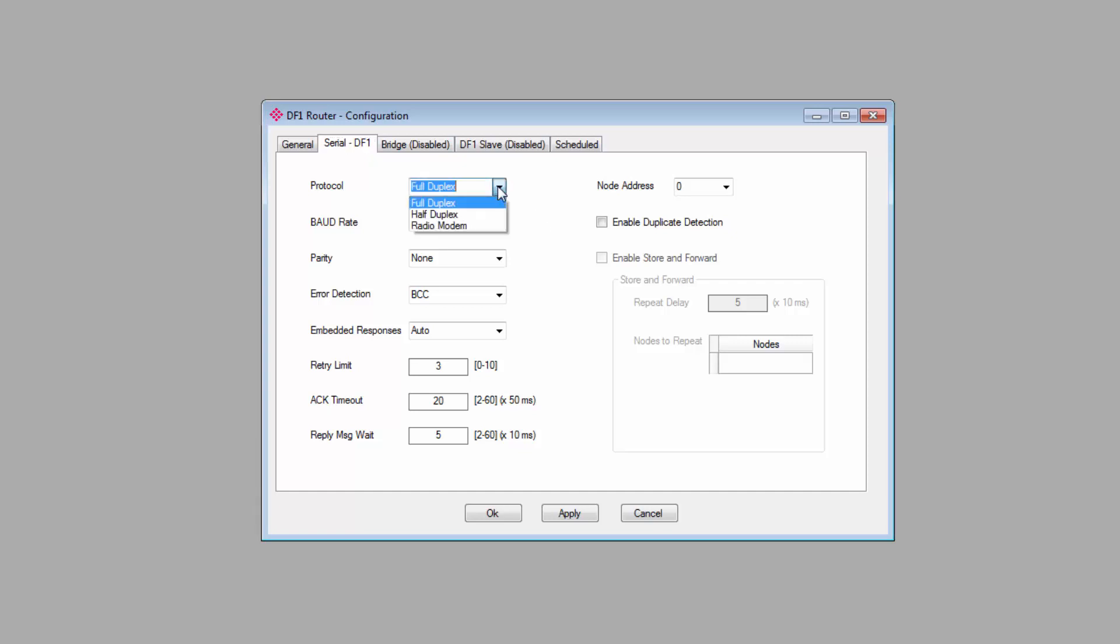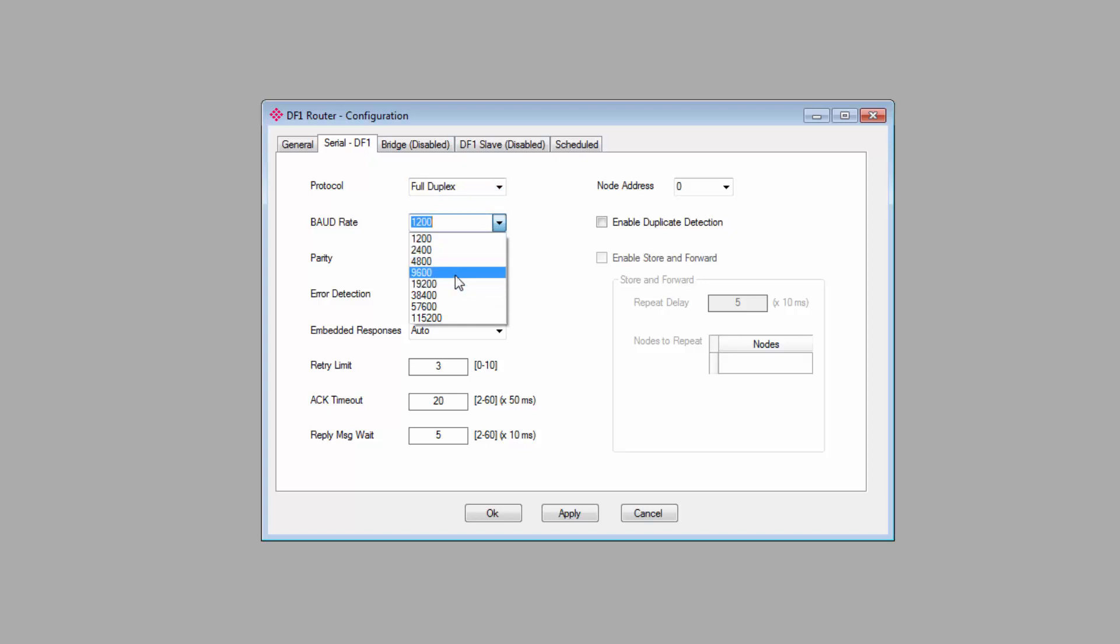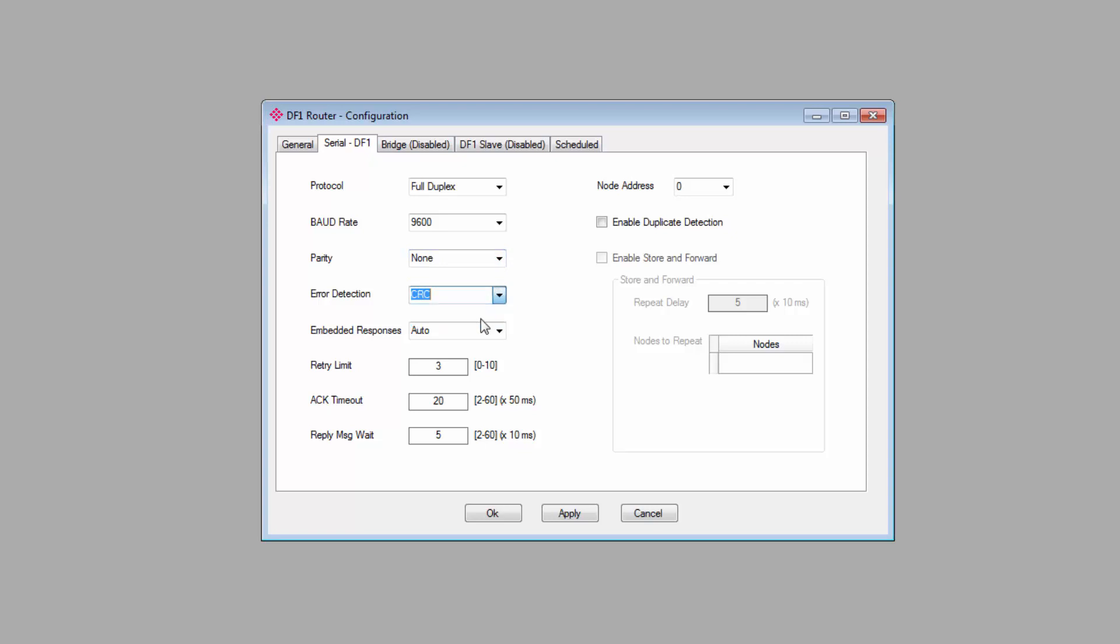For Protocol, I'll select Full Duplex. Baud rate will be 9600. Parity will be none. I'll set the error detection to CRC. Embedded responses, retry limits, and timeouts—just set to whatever you need.